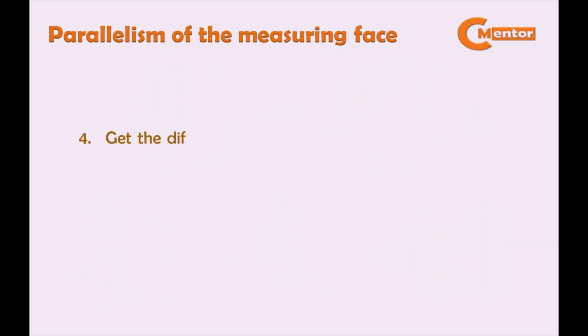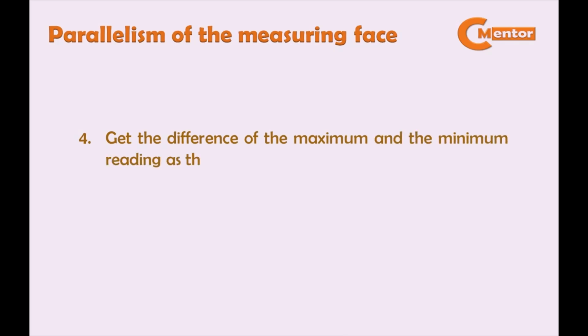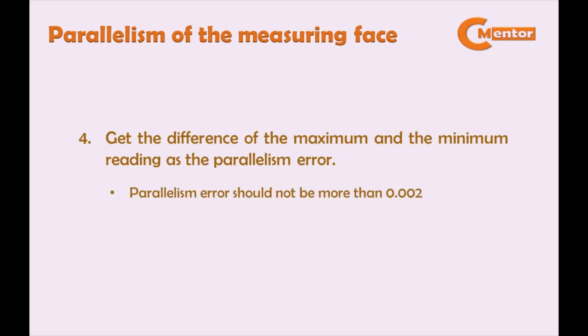And lastly, get the difference of the maximum and the minimum reading as the parallelism error. Parallelism error should not be more than 0.002 mm. For the last video, this is to show you the actual procedure for the parallelism of the measuring face.